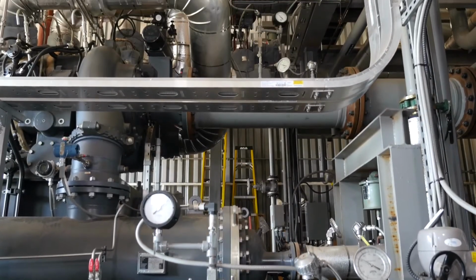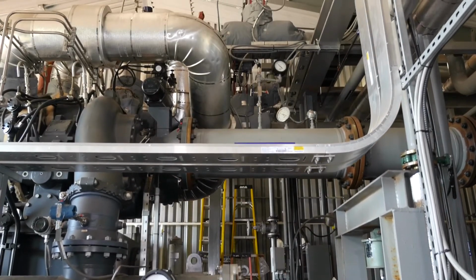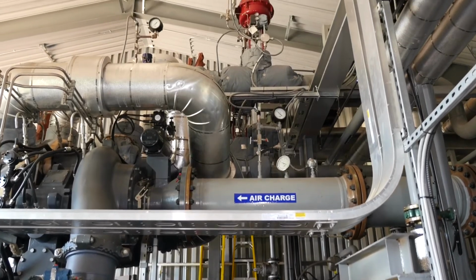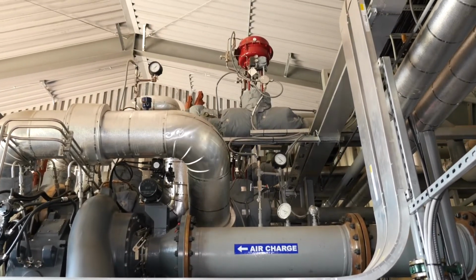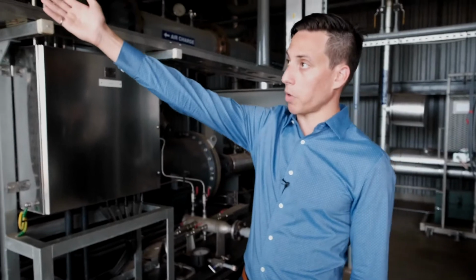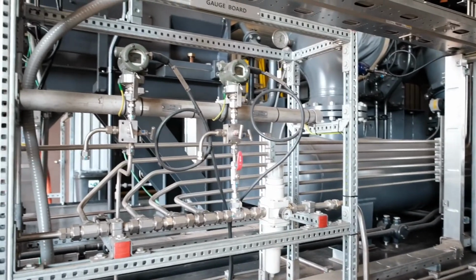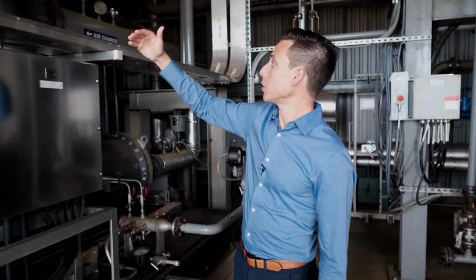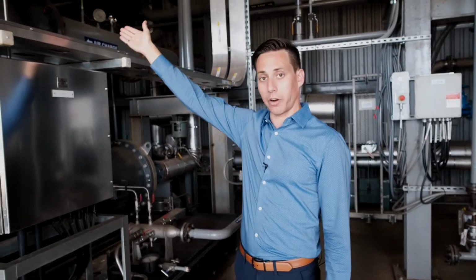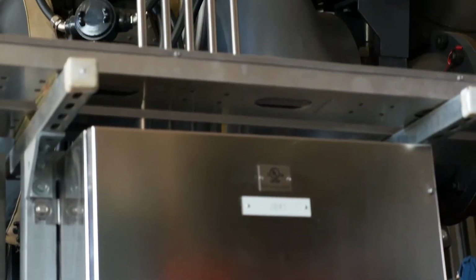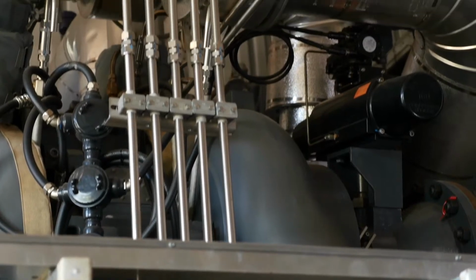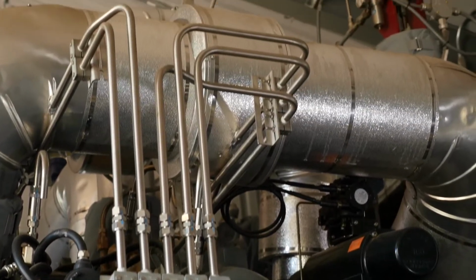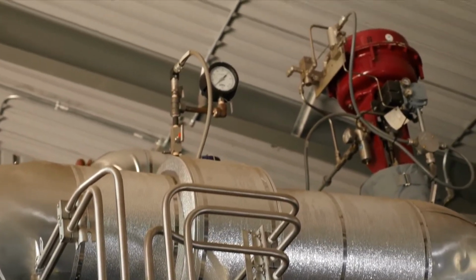The compressor is a 5-stage, integrally geared, electrical motor-driven unit. Electrical energy comes in from the grid through the transformer into a cable into the electrical motor. The motor converts that electrical energy into a spinning mechanical energy of the shaft. That shaft, in turn, spins a large central gear here in the gearbox. That gearbox distributes the power amongst several smaller gears spinning around the periphery of the central one, each one of them with several impellers off either side.